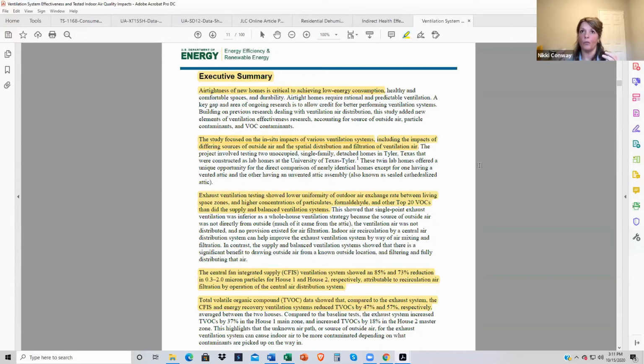And I always want to look at what's happening with our buildings when we have moisture issues, and take steps to make sure that when we apply a dehumidifier, it's going to be successful. If we're running continuous exhaust-only ventilation, let's try to go to intermittent, or occupied times - try to minimize that a little bit and see what that does to our numbers, with the understanding that that might not be the healthiest strategy for the people in that home.